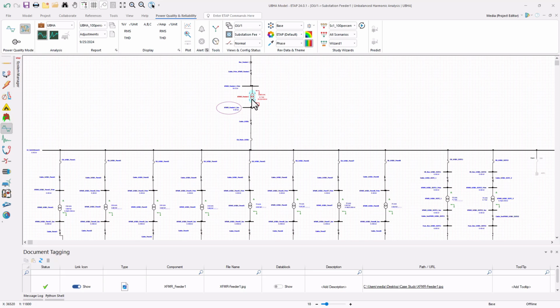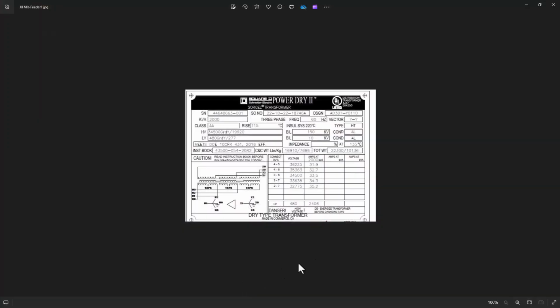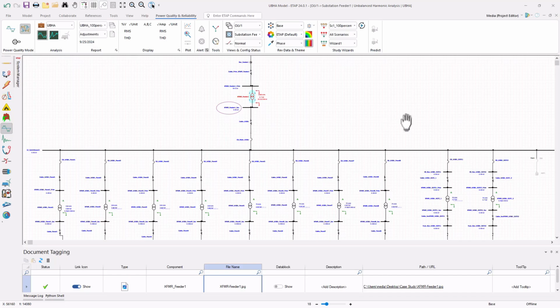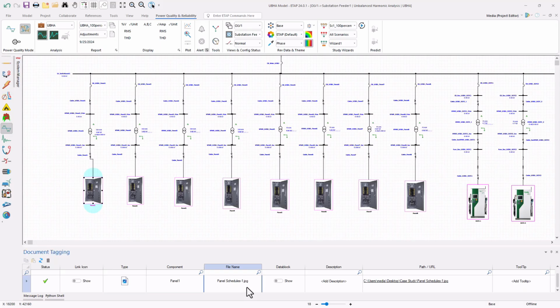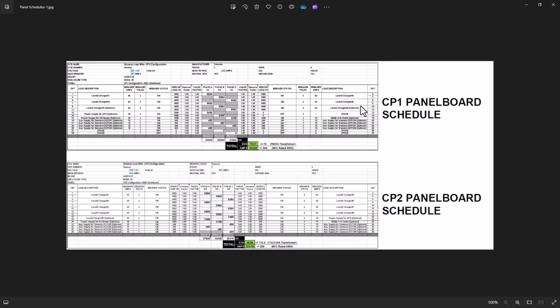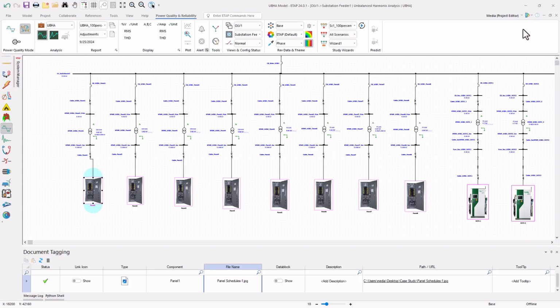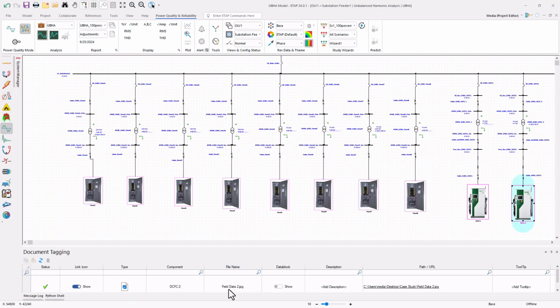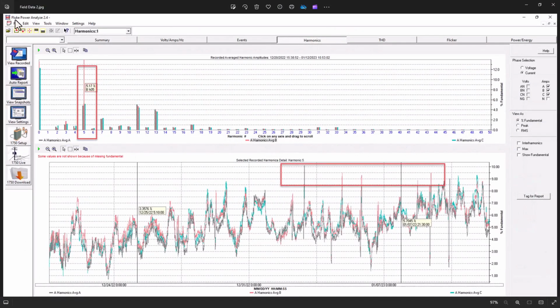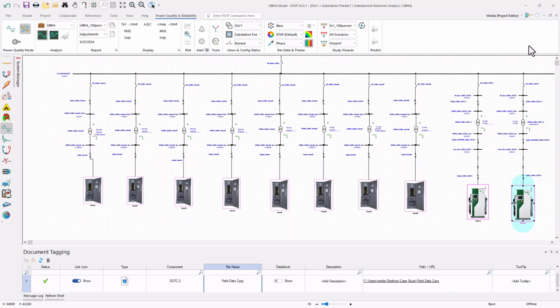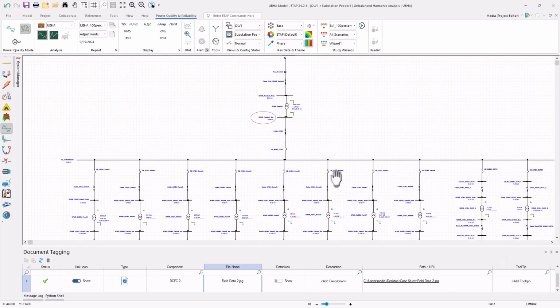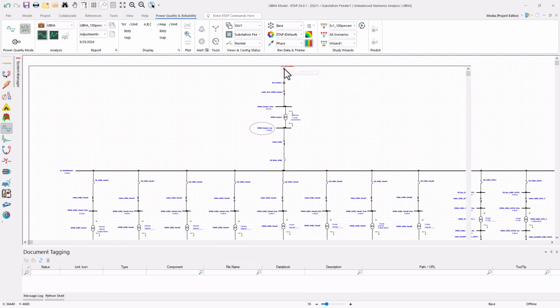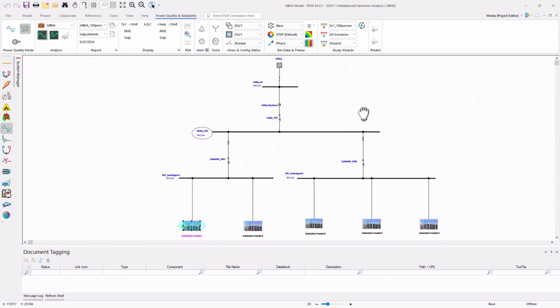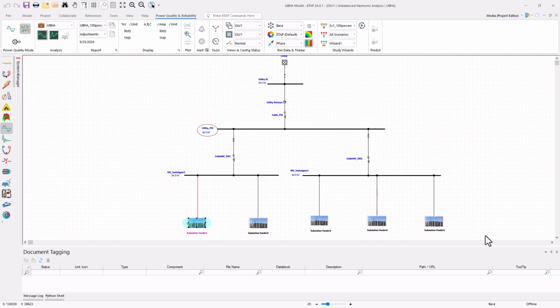Once all the available data was received from the client in the form of electrical permit drawings, equipment data sheets from the manufacturers, panel schedules showing different charger configurations of level 2 and level 3 chargers, field measured data of harmonic distortion with the PQ meters that were installed in the field, and equipment photos and reports from other system studies, we started developing ETAP digital twin models of each of those sites. So the one that we're seeing right now is a replica of the digital twin model of one of those EV charging sites that were analyzed.